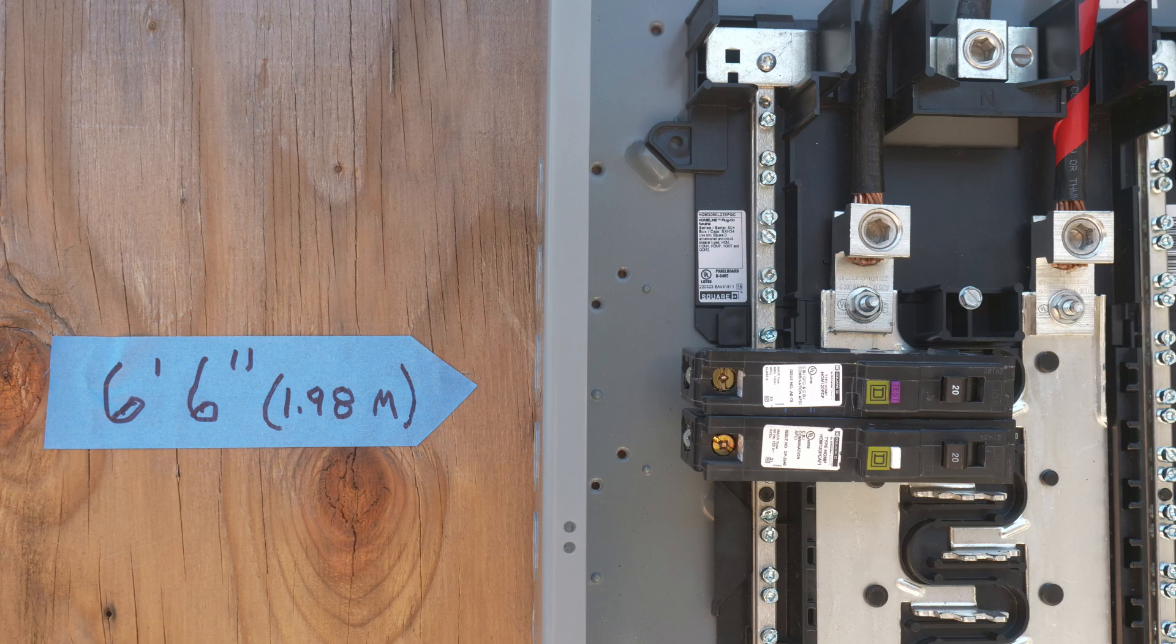As for this panel, for example, since the highest circuit breaker is 6 foot 6 inches off the floor and there is no main breaker, then it would pass as far as height is concerned. However, if it was 2 inches higher it wouldn't. Thanks, I hope this video was helpful.